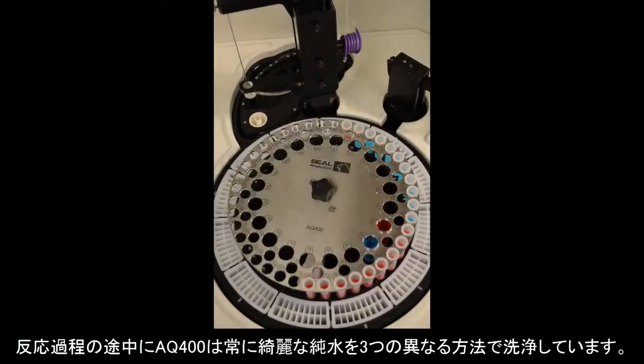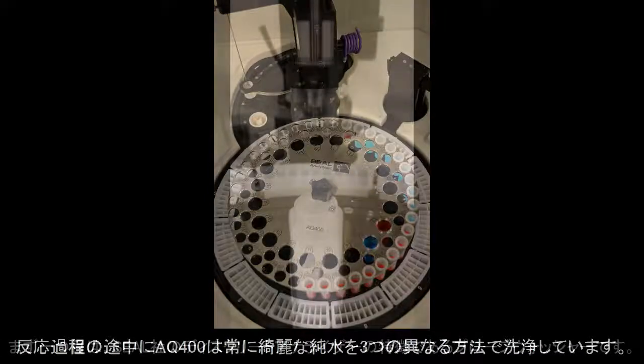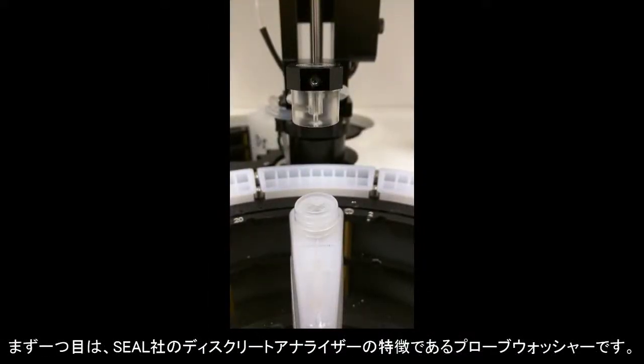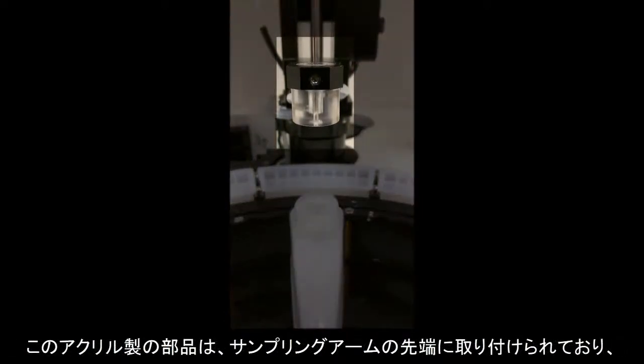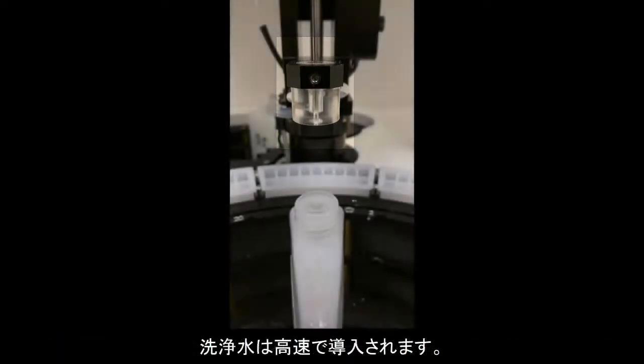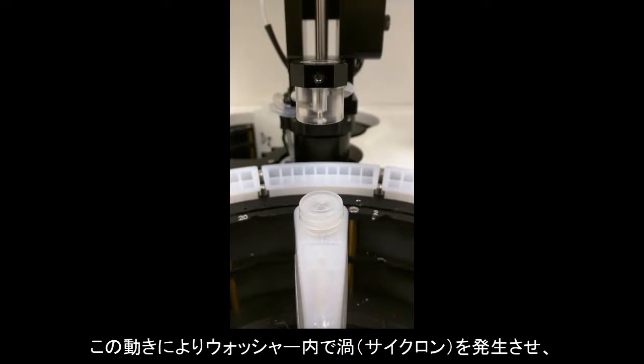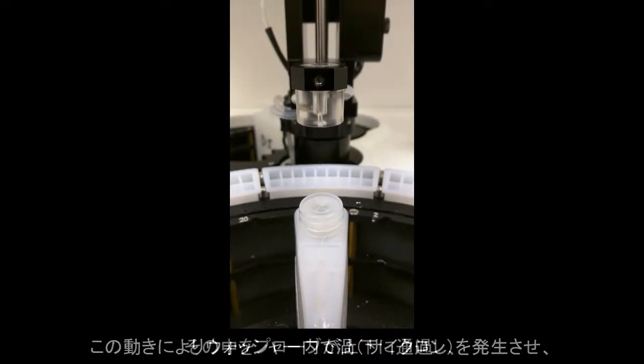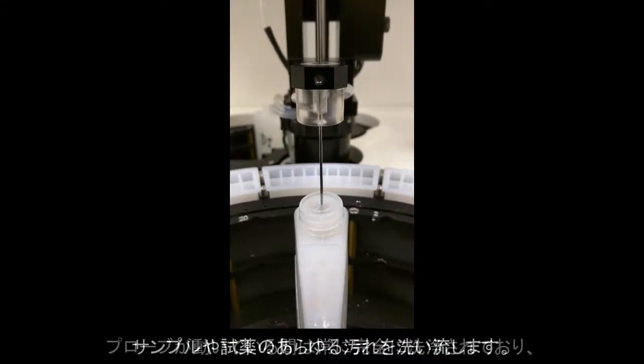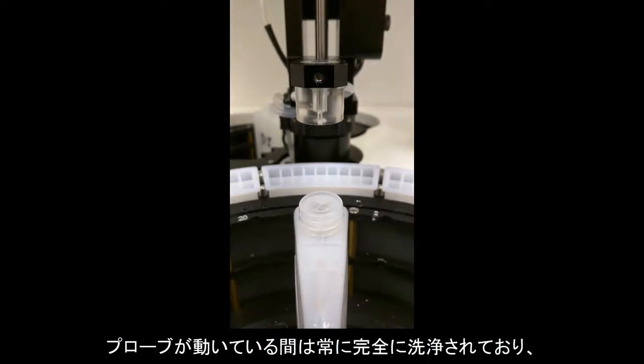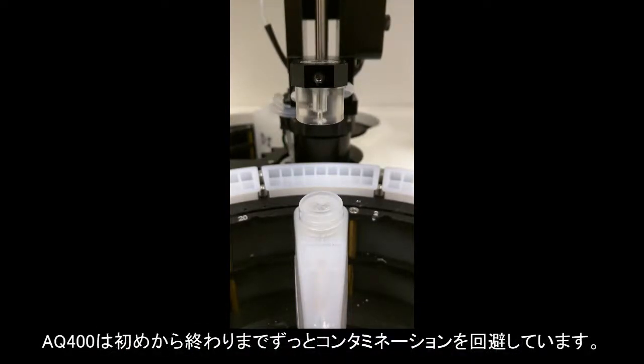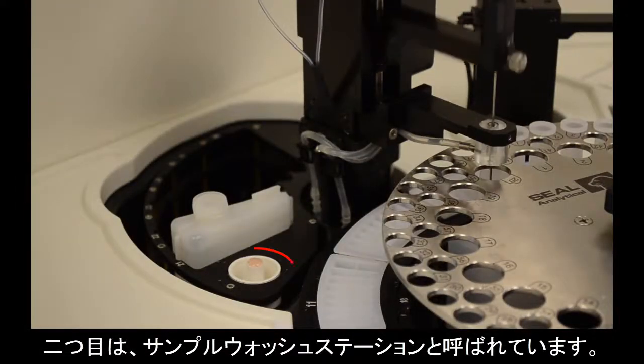During this entire reaction process, the AQ400 is constantly cleaning itself with fresh water in 3 separate ways. The first place, which is unique to Seal Analytical's discrete analyzers, is the probe wash assembly. This acrylic assembly sits at the base of the probe on the sample arm, and water is pulled through at a high rate of speed. This creates a cyclone, and as the probe moves up and down through the probe wash assembly, it acts as a squeegee and cleans off any droplets of sample or reagent. By completely cleaning the sample probe before any movement of the sample arm, the AQ400 is able to eliminate front-end contamination.